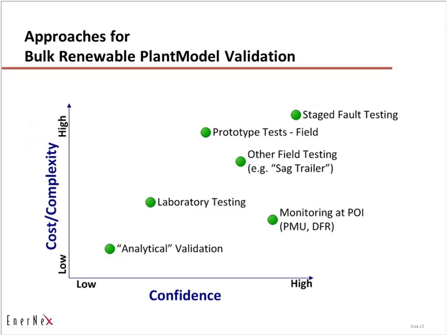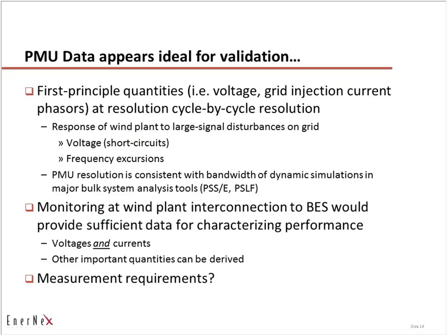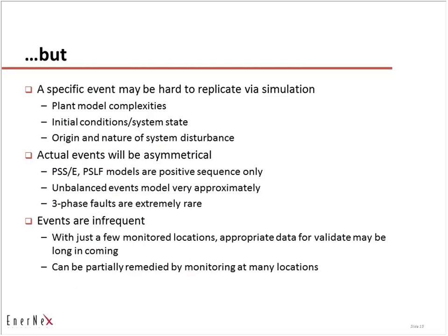We can't do staged fault testing anymore, obviously. It appears that monitoring at the point of interconnection with PMUs, digital fault recorders, or similar instruments is likely the best chance to really validate a plant model. The difficulty is that the events we experience won't be neat and tidy, and probably won't be balanced. There's going to be a lot of technical work to even utilize that data. At the same time, it's a real grid disturbance and we need to make sure that what we're representing in the planning models comports reasonably well to the behavior of an actual plant.